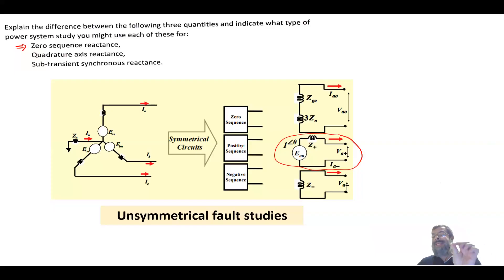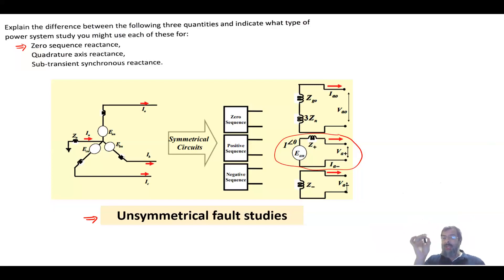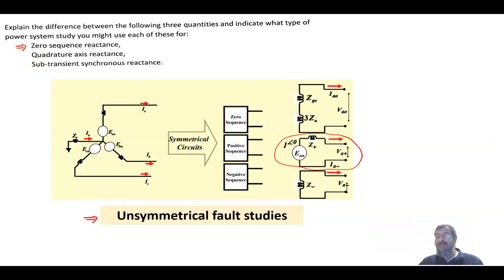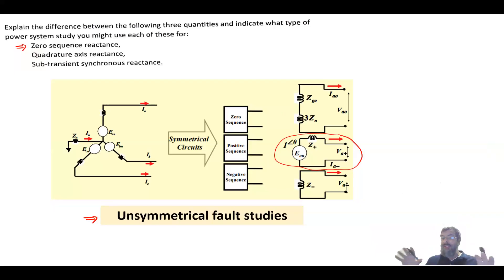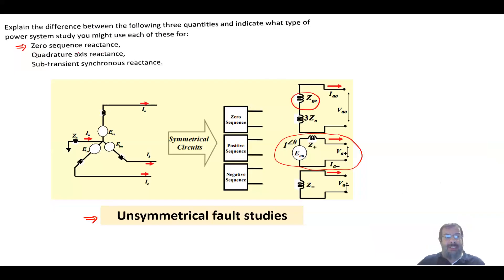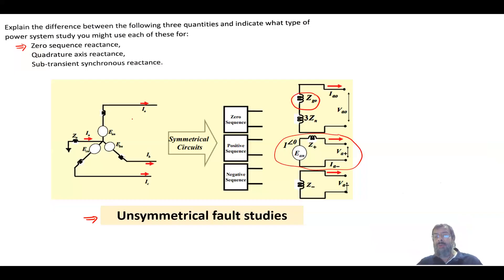When the system is subjected to an unsymmetrical fault — like single line-to-ground, line-to-line, or line-to-line-to-ground — the system becomes unbalanced. To analyze it, we decompose the circuit into three different circuits: zero sequence, positive sequence, and negative sequence. The model for the zero sequence does not have a voltage supply — it has the zero sequence impedance of the generator. This is what is meant by the zero sequence reactance, used to model the generator.